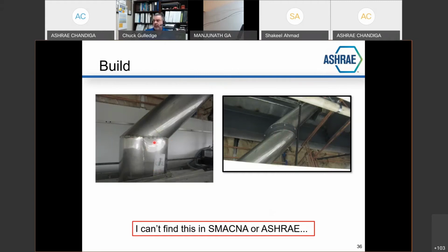All of this was created by somebody who had the brilliant idea late in the game that instead of the fume hood being located vertically straight down where it was supposed to be, somebody's cabinet layout wanted to modify it, so they moved it in the field, and the plumbing gases for the hood all got reworked, and the mechanical came back and did this. Brilliant. Obviously, we had a problem with flow on that hood.